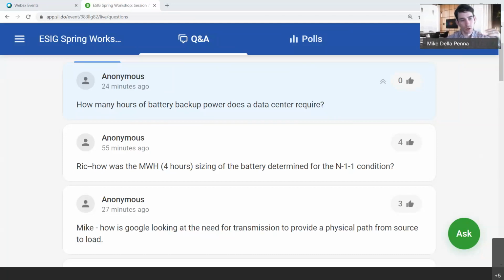As we reduce the load, as we modulate our consumption on the back end, such that when we have run out of duration of the battery, we're now at a point where the load is not going to outstrip the capacity of the remaining diesel generators. So it's sort of a hybrid solution. I didn't get into a ton of detail because it's somewhat internal, but you can think of it as a relatively shorter duration lithium ion battery paired with fewer diesel generators that works in concert with the software layer.